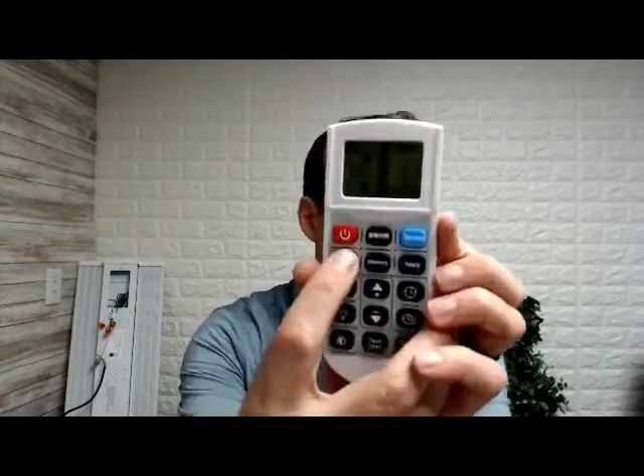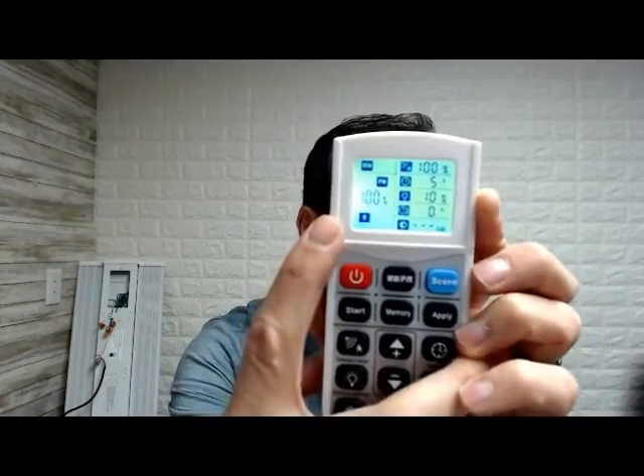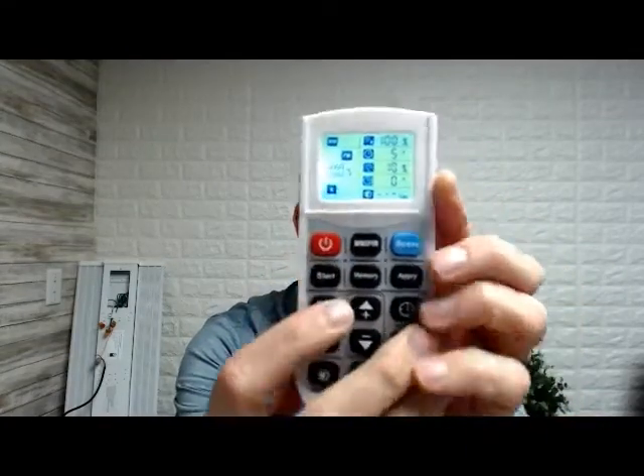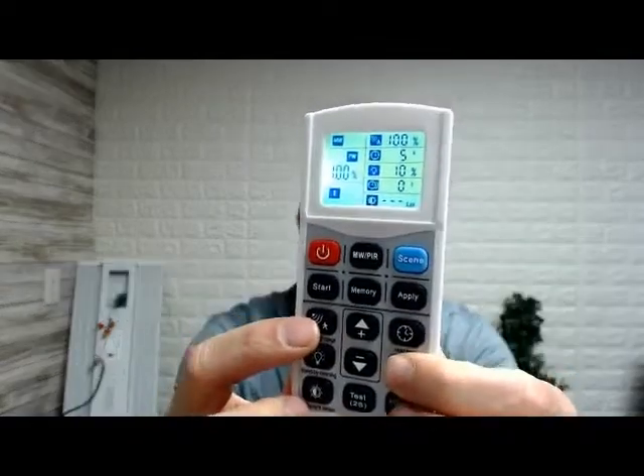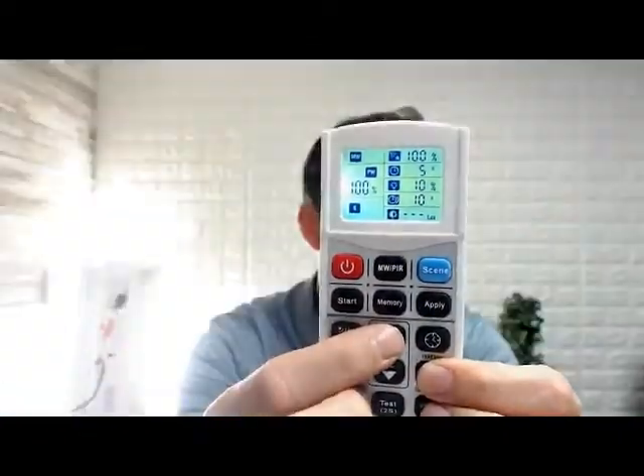Now if you're like, no, I want it to dim down to a certain level for a certain period of time, then I want it to dim back up, we're going to come back into our remote, we're going to press the start key again, you can see it blinking right there on the side, the start is blinking, and now I'm going to adjust my hold time, or my standby, I'm sorry, my standby time, and I'm going to adjust that one up to 10 seconds.